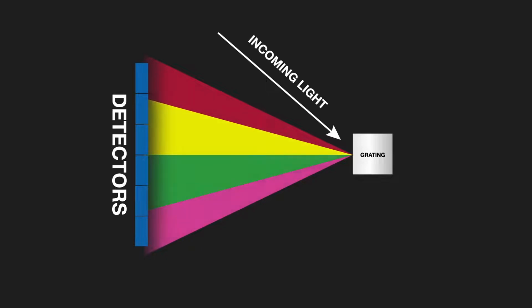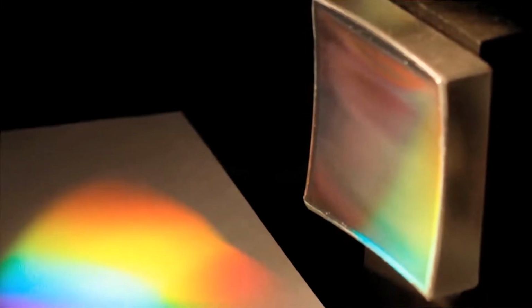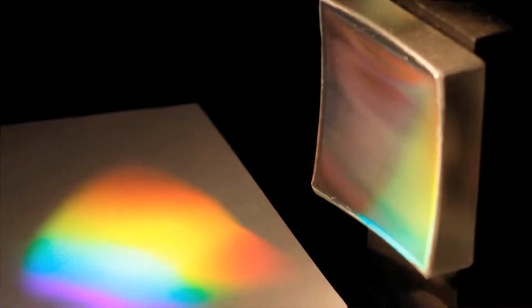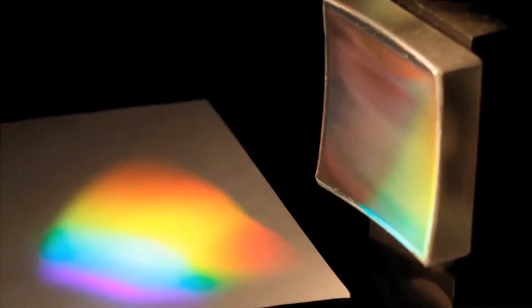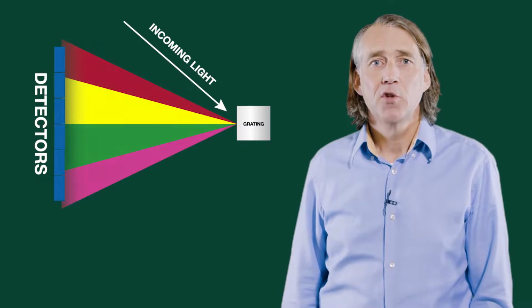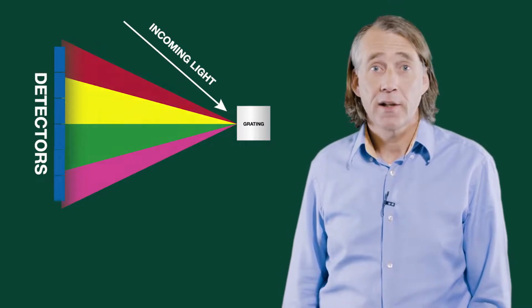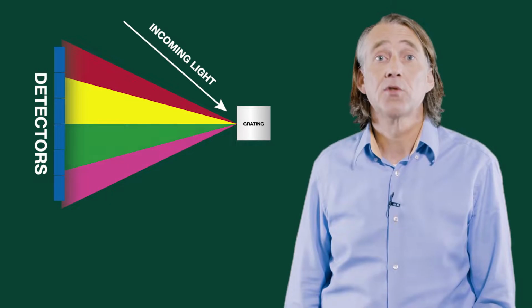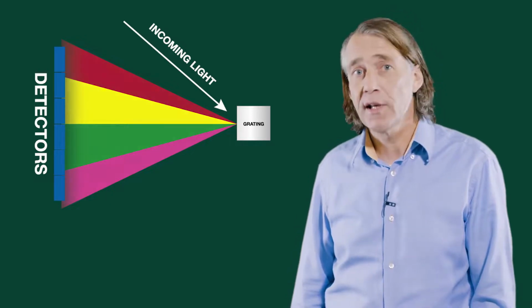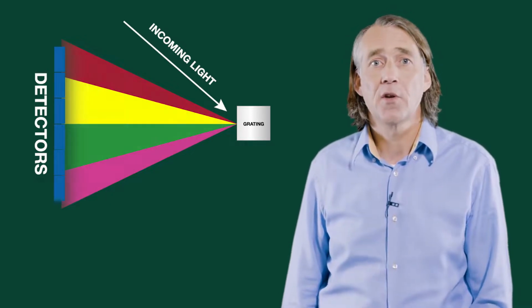The characteristic light emitted by the atoms in the sample is transferred to the optical system, where it is split into its spectral wavelengths by the high-tech grating. The grating contains up to 3,600 grooves per millimeter. Next, the individual spectral line peak signals are collected by detectors and processed to generate a spectrum showing the light intensity peaks versus their wavelengths. This means that OES provides qualitative information about the sample measured.